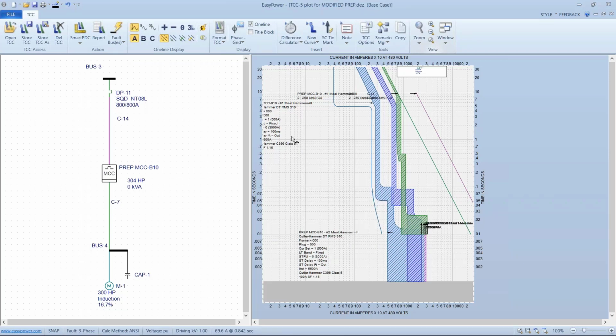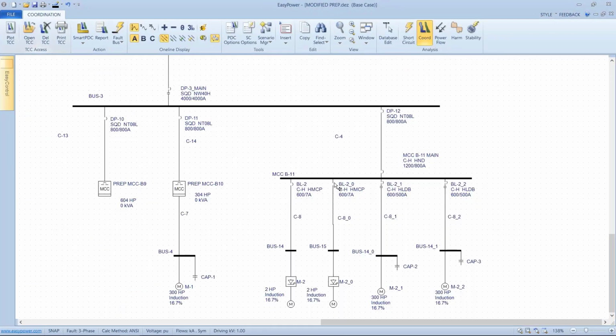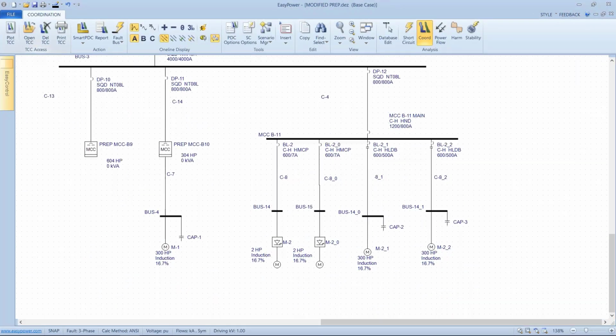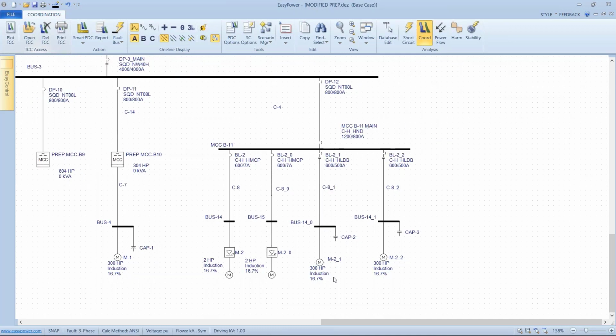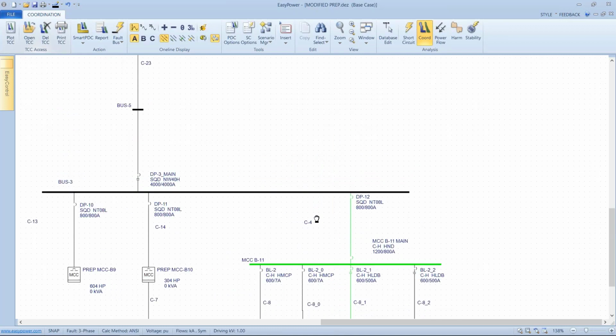All right, so I'm starting to wade off into the weeds, so I apologize for that. But where I wanted to leave this was, in a very complex system, at least outboarding the largest load and then not confusing it with the other loads that may potentially be inside the motor control center is a good way to go.